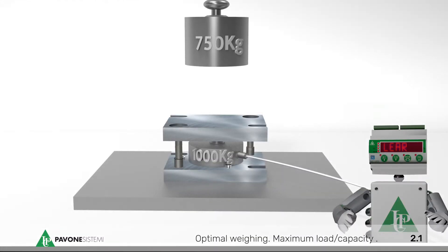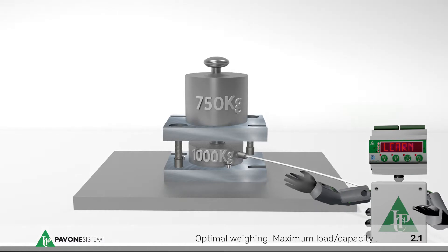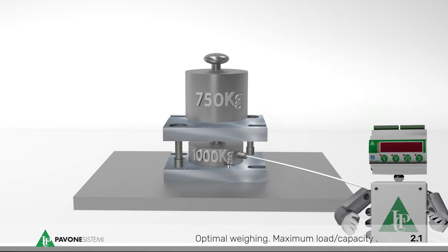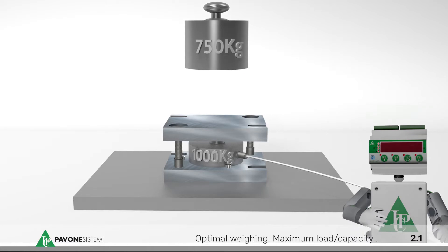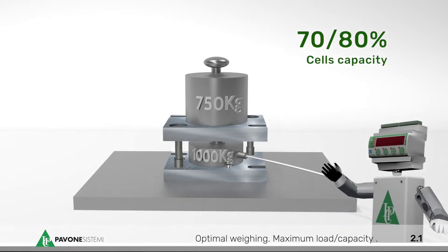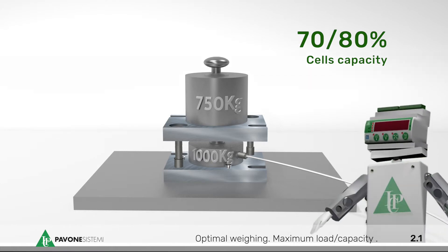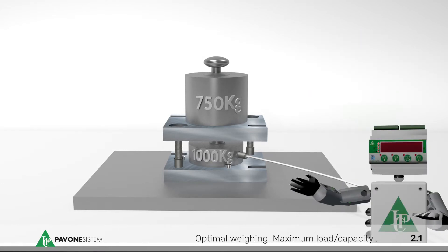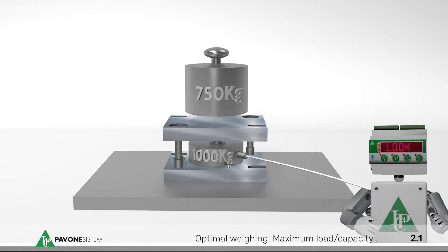The correct calculation of the capacity of the load cells is essential in order to get the best performance from the weighing system and to guarantee a long useful life to the same system. We recommend to use the load cells at a maximum of 70-80% of their normal capacity and to regularly check that they are correctly oriented while the installation is being carried out.